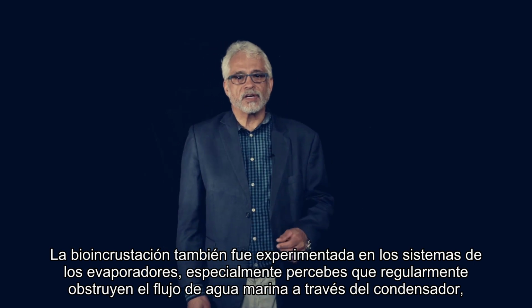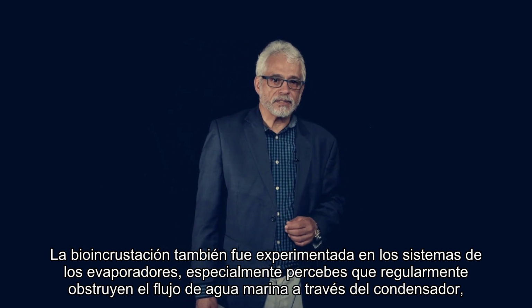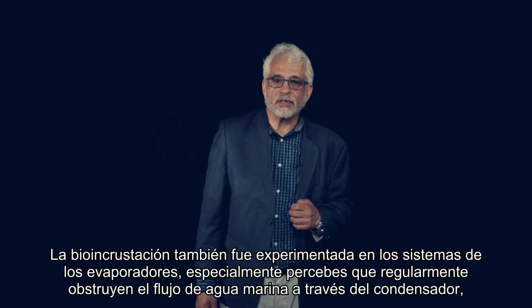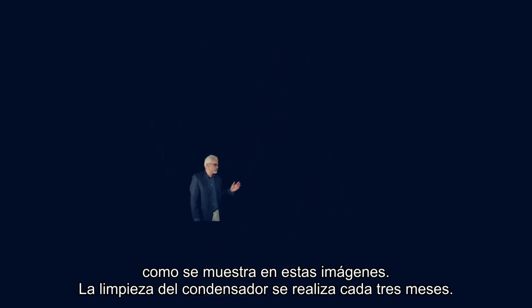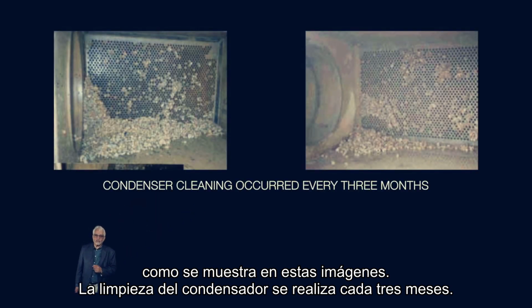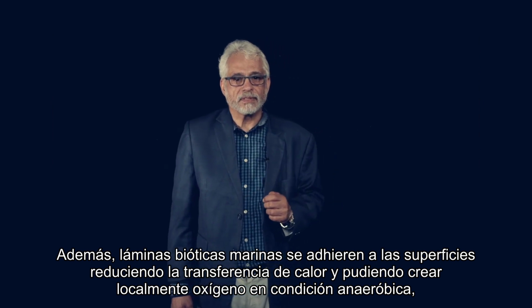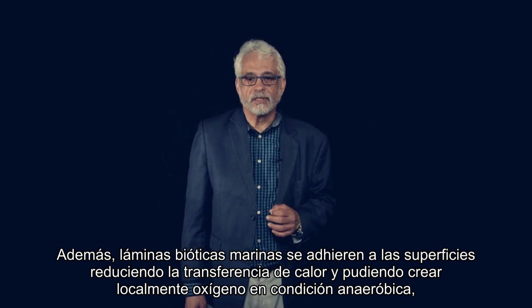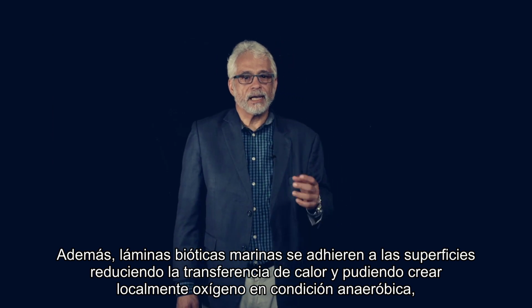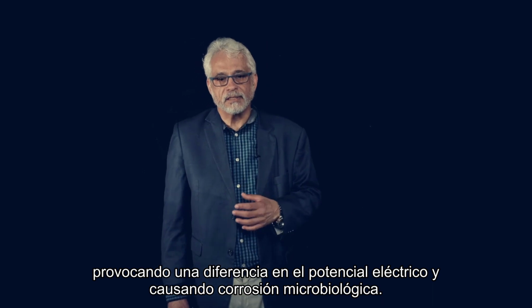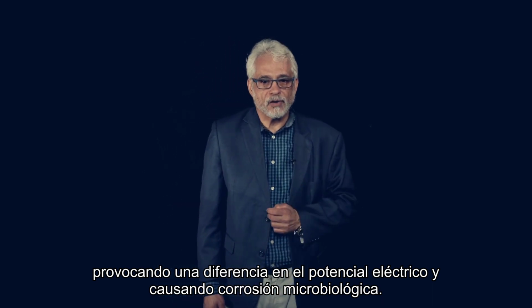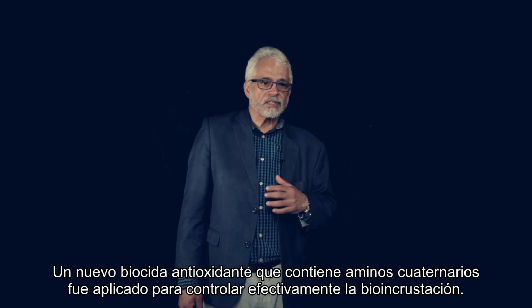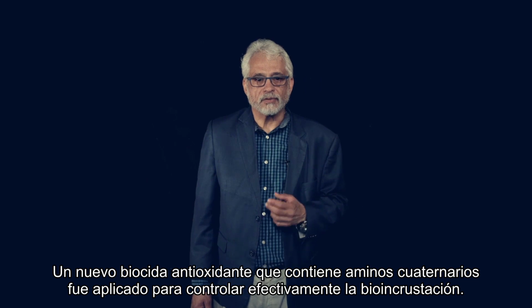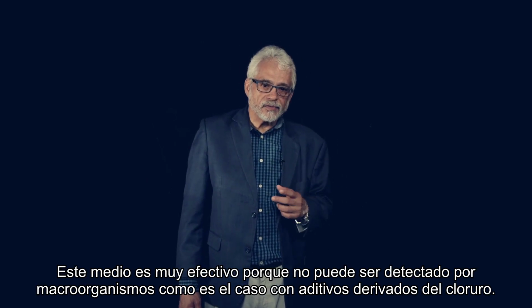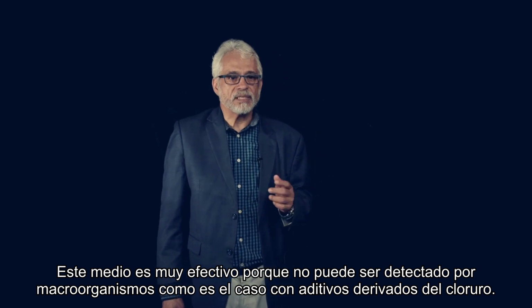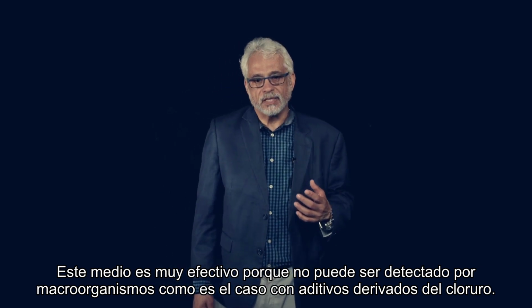Heavy biofouling was also experienced in the seawater intake system of the evaporators. Especially barnacles regularly obstructed cooling water seawater flow through the condenser, as shown in these pictures. Condenser cleaning occurred every 3 months. In addition, marine biofilms attached to the tube surfaces reduce heat transfer and may create locally oxygen depletion at anaerobic conditions under a biofilm, creating a difference in electrical potential and inducing microbiological corrosion. A novel non-oxidizing biocide containing quaternary amines was applied to successfully control biofouling. These cationic surfactants are very effective because they cannot be sensed by macroorganisms, as is the case with chlorine additives.